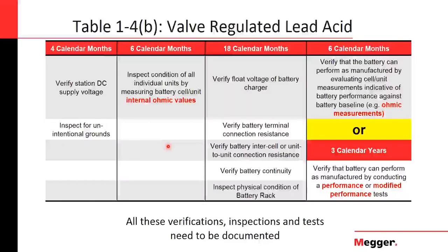Okay, the next table is pretty similar to the previous one. It is for the valve regulated lead acid batteries, VRLAs. You have the same schedule, 4 months. Well, you have one more period there, 6 calendar months, 18 months, and then you have the verification of the capability of the battery to perform as the manufacturer's specs.